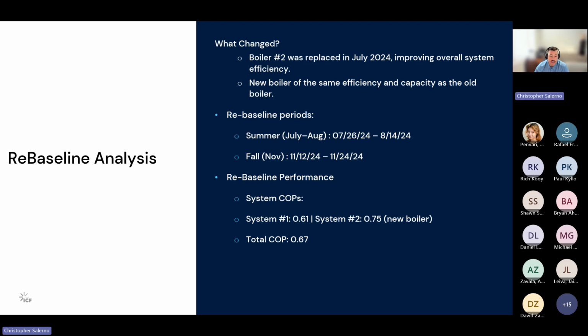And so the rebaseline performance, system 2 actually, even though it was a much newer boiler, the system efficiency only went up to about 0.75 due to the system dynamics and the system design in itself. So the overall system COP only went up from 0.62 to 0.67, but it was important to be able to characterize that for any efficiency gain analysis that we'll be talking about shortly.